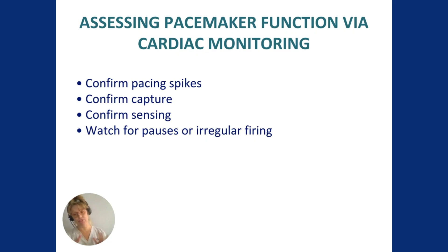So there are 3 core pacemaker malfunctions to recognize. Failure to pace: no pacing spikes when the heart rate drops below the set rate. Failure to capture: spikes are present, but no QRS follows. The pacemaker fires, but the myocardium doesn't respond. Failure to sense: the pacemaker doesn't recognize intrinsic beats and fires at the wrong time. So at the bedside, remember: no spike, failure to pace. Spike without a QRS, failure to capture. Spike at the wrong time, failure to sense. Rapid recognition helps prevent instability. We're going to dig into these a little deeper.